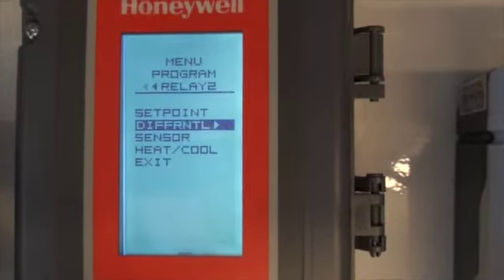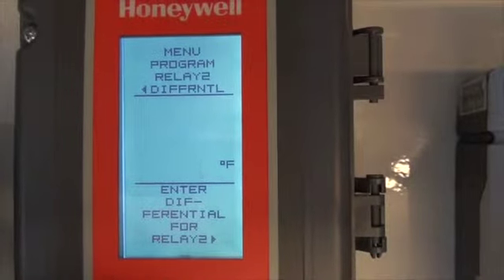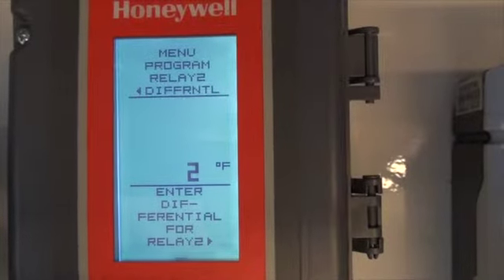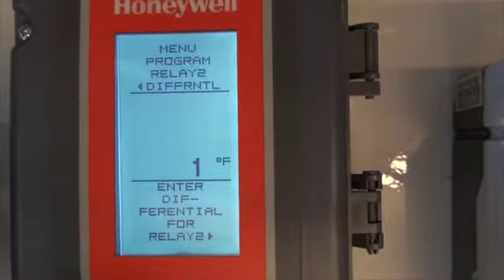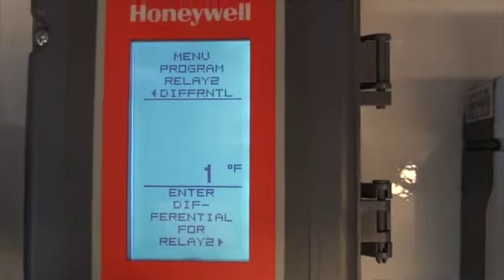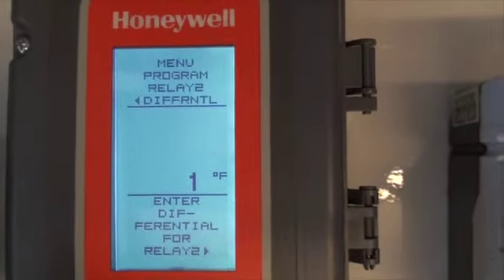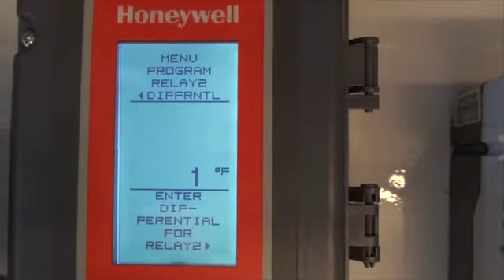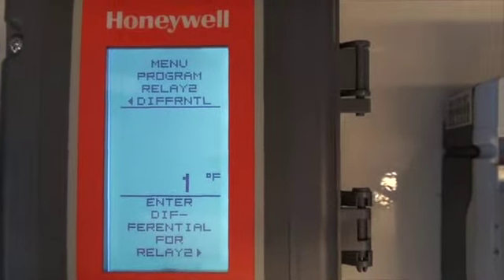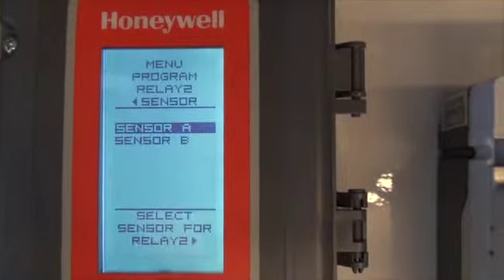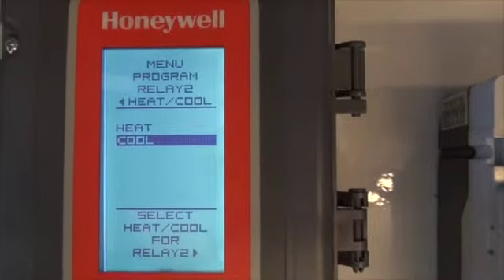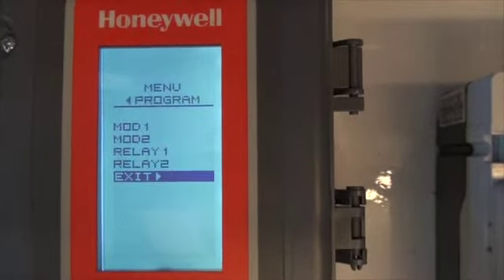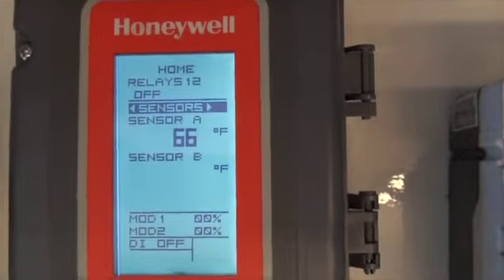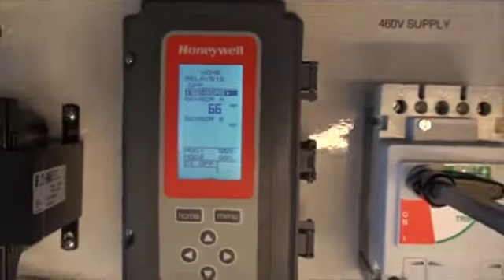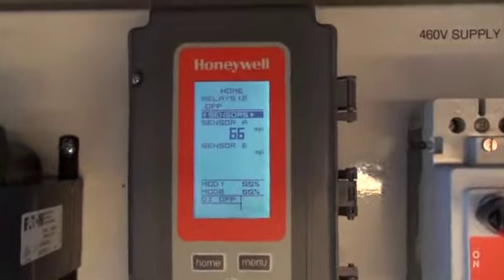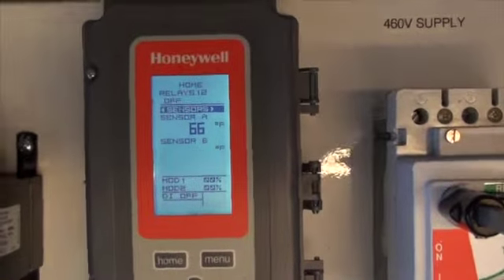Okay, hit the right arrow key. The differential, I'm only going to put a 1 degree differential in that because again, since we're just enabling the drive and we're relying on the ramping of the drive up and down to operate the fan motor, I'm not going to worry about differential so much. I'm going to set a 1 degree. Don't want a big differential there. Okay, set sensor A, it's definitely got to be in the cooling mode again, and I'm right arrow keying down. And basically that's it. That's the entire programming of the Honeywell T775 controller. Very easy to do, very easy to set the set points.